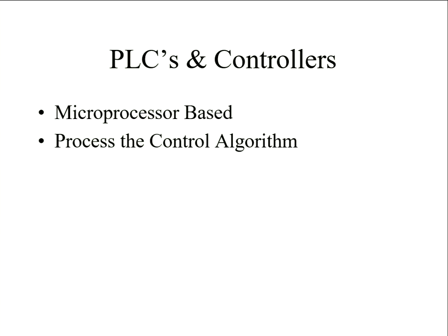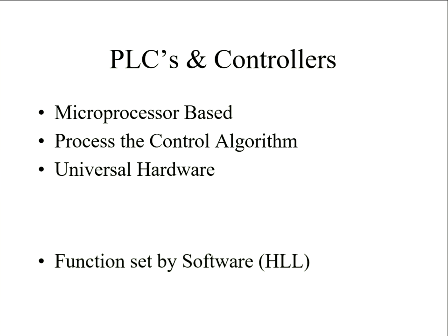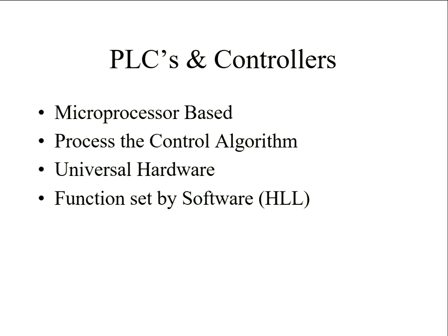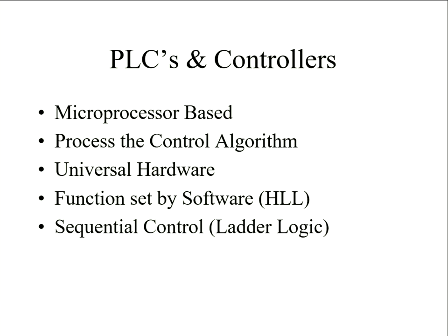Some of them will do many loops. I'm not necessarily talking about multi-input, multi-output, but you might have 4 flow control valves, and you can do all 4 in one controller if that's what you desire. And this is an example from Eurotherm, a well-known company in that area. This was simple flow control. It's like a modular box. It could slide into a cabinet, but it just does a single loop. It's got a process display there. These buttons will allow you to put it into auto or leave it in manual, and raise and lower set points. You can look at what your set point is. It'll generate a few alarms for you if necessary, but isn't terribly complicated.